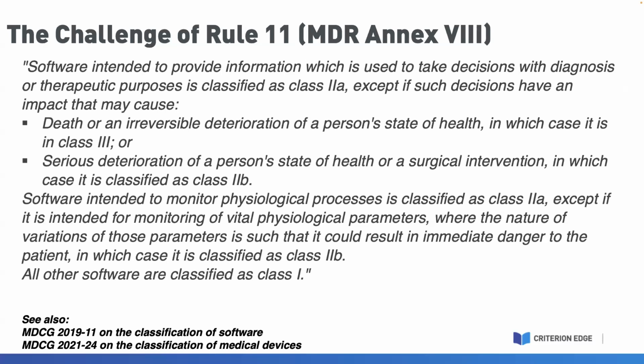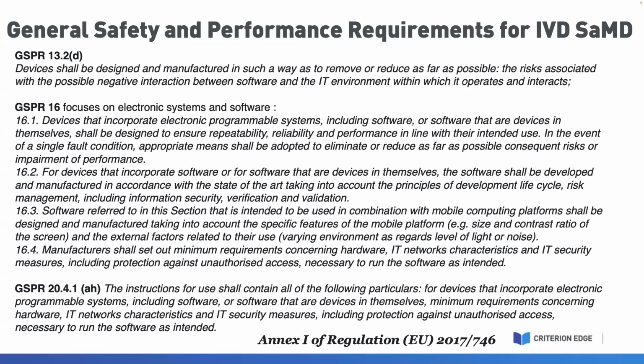Okay, and finally, in the last slide that I'll present before we get to our question and answer session, I wanted to just point out the general safety and performance requirements, because in the EU, once the software qualifies as an in vitro diagnostic medical device, you must demonstrate compliance with the GSPRs that are outlined in Annex 1. If some of them aren't applicable, you should be prepared to provide justification.